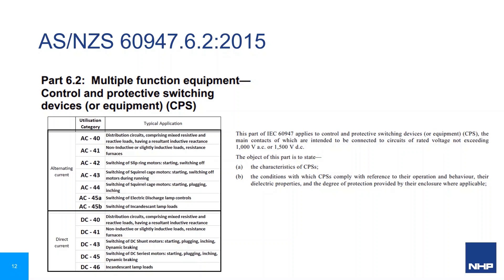CPS devices are defined in IEC 60947 part 6.2. These are devices which have one set of contacts used for control switching functions, but are also used to open upon over-current protection commands — i.e., they are a combination contactor and circuit breaker. The utilisation categories are similar to the functions assigned to electromechanical contactors.